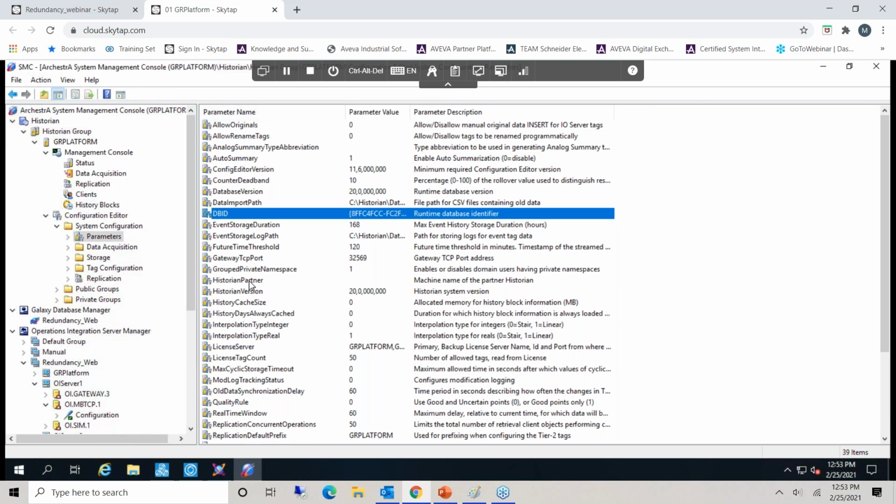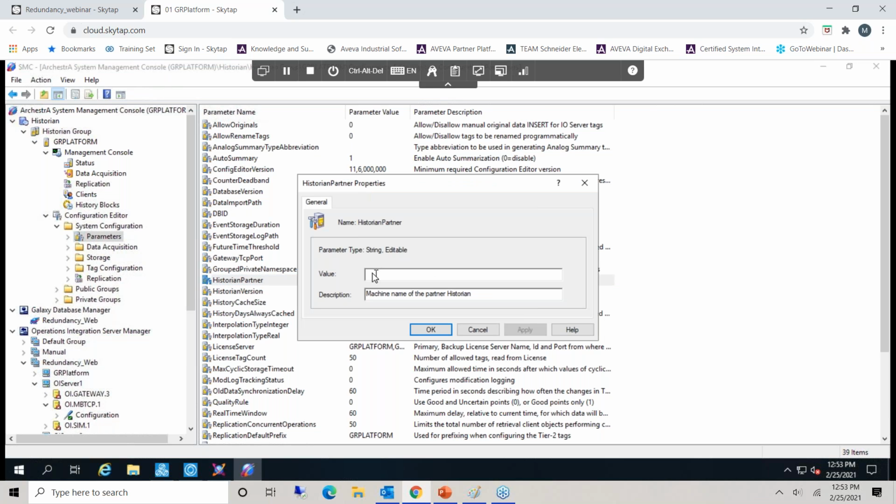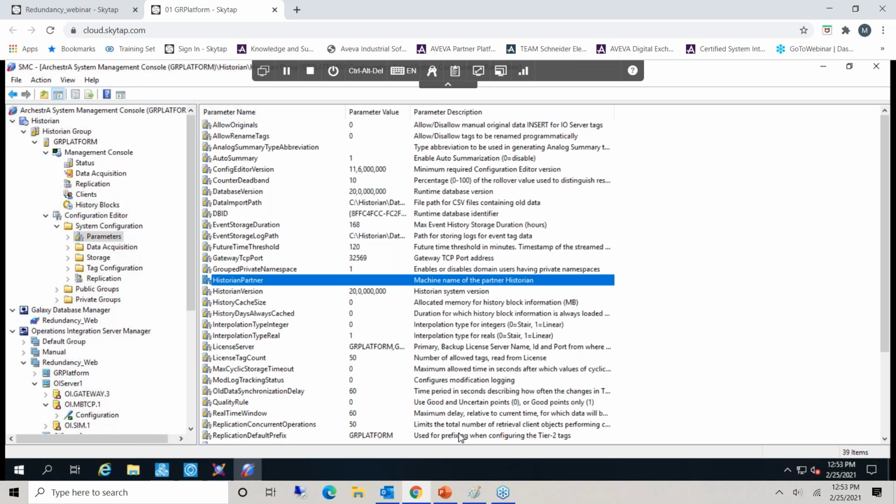Okay, Munzir, thank you. I found it. Historian partner. So you go here, double click. This is the name. You put the name of the partner machine, the other historian. You put here where your partner is, and you go there and put the partner here. But remember, again, for the historian, all the configuration must be replicated here and there. The same configuration for historian 1 must be replicated for historian 2.